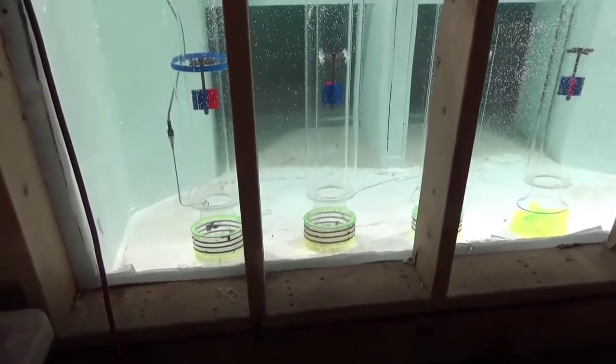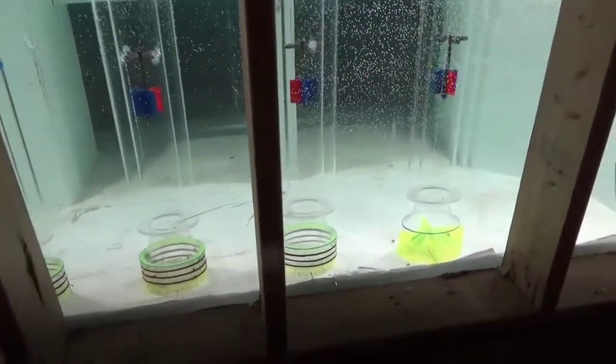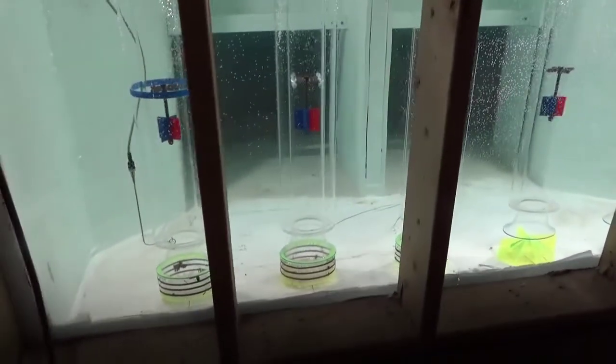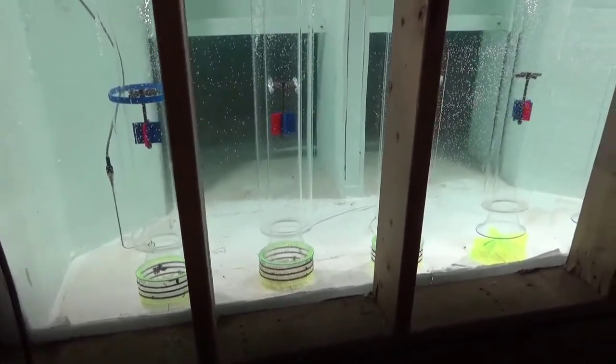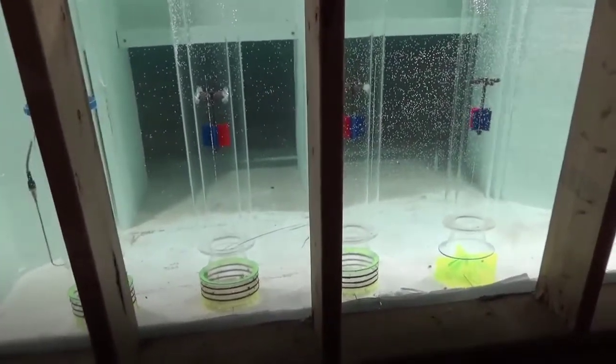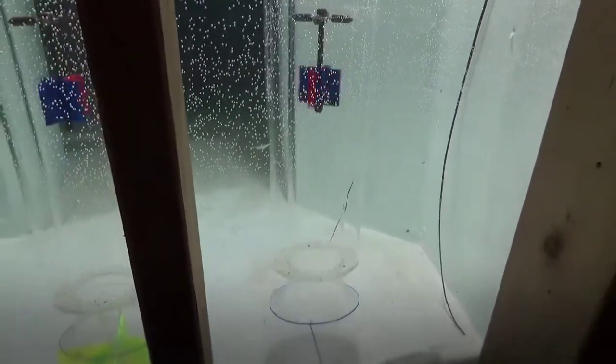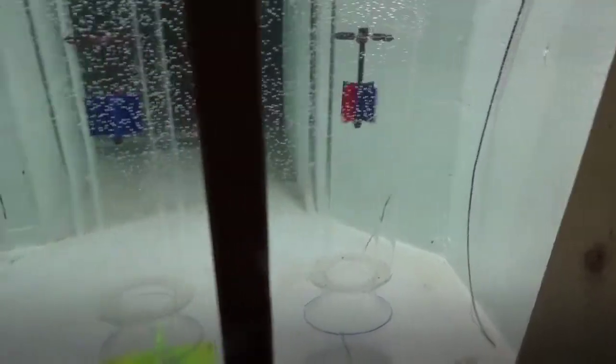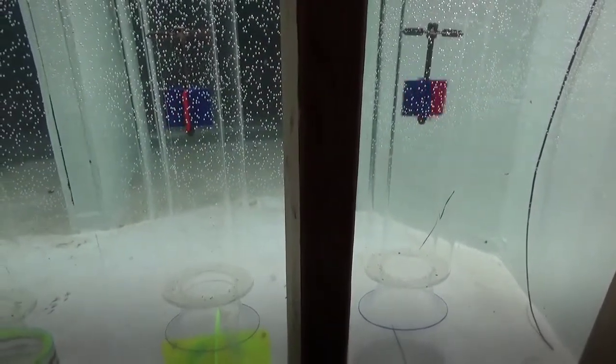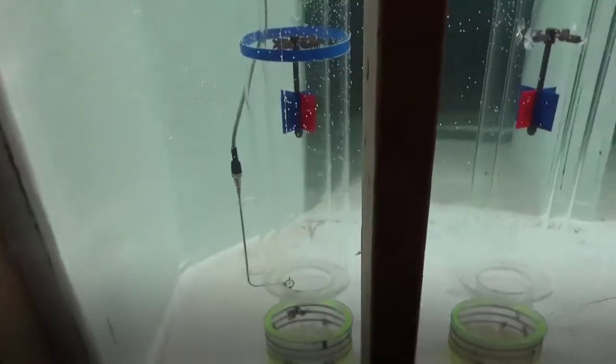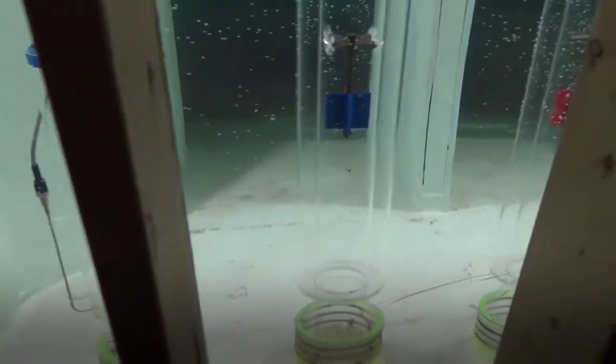Okay, just a little bit more video here. We're going to make note of a couple of things. So a second ago, we were running 20,000 GPM per pump, which was the rated design condition. We've dropped this down now to 60,000 total. We've got the same 4 pumps running, so this pump's now running at 15,000 GPM. You just see the rotometer's really still spinning. A little bit unsteady over here, and this one next to it. Over here, no pre-swirl at all, just a little bit in this one.